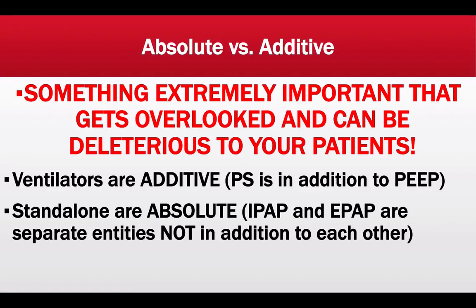One of the most important points in this presentation is to address additive versus absolute when it comes to invasive versus non-invasive ventilation. This is extremely important, often gets overlooked, and can be deleterious to your patient outcomes. Ventilators are additive as far as pressure support and PEEP — pressure support is in addition to PEEP. However, on standalone machines, they're absolute: IPAP and EPAP are separate entities and are not in addition to one another.